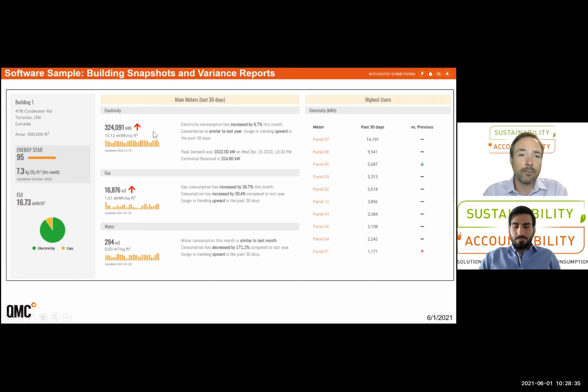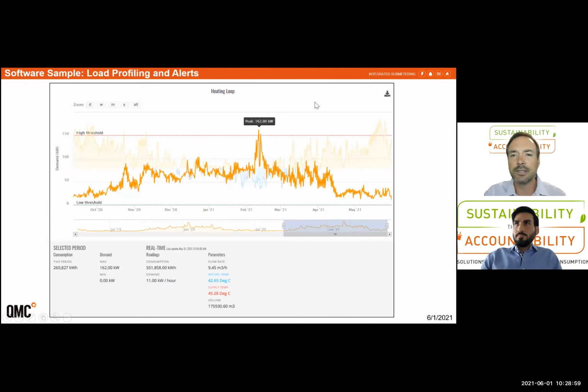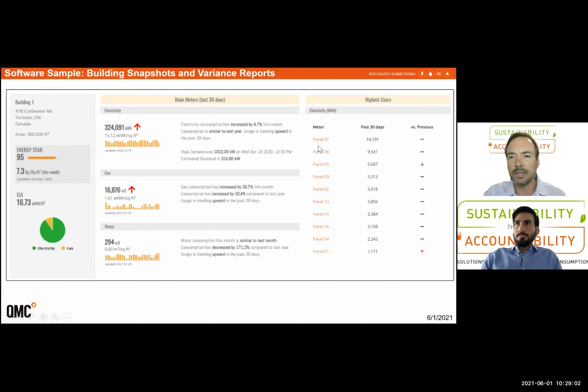This is a sample of, I believe it was building 1 here, where you go in and can see the consumption of these different loads at a building level. You're able to see if there's an increase or decrease in their consumption, not only month over month, but also the same month of the previous year. And as you can see on the right side here, some of the critical loads within the building are also shown. If there's a variance in their consumption, you're able to see an increase or decrease there. Fully automated reports can also be sent showing every meter point within a property and their plus or minus variance over a week or a month or any period you choose.